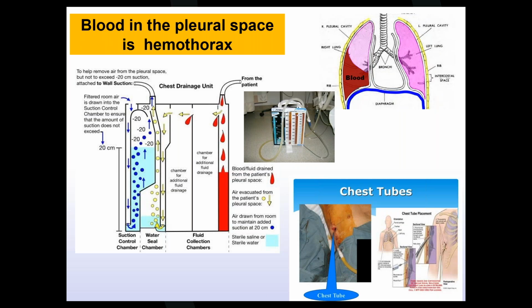And the sweet thing about it, it's just a passive device, but the way the chambers are set up, there is a water column that is filled up, and the height of the water column limits and dictates the amount of vacuum. Because you clearly wouldn't want to just take 100 millimeters of vacuum from your wall and try to suck on somebody, their guts would come out of that. So you don't want to do that. But these drainage units with that column of water basically regulate the wall suction to a safe level depending on the height of this, typically 20 centimeters of water.